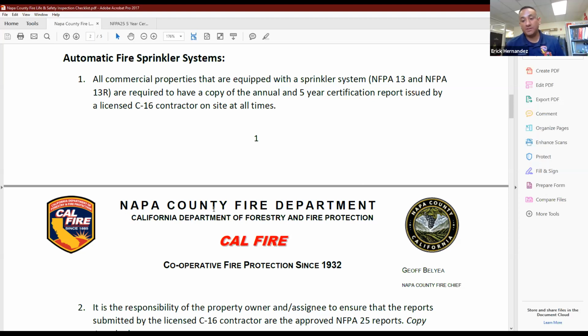So with the exception of 13D, all 13R and 13 systems are required to be inspected on an annual basis by a C-16 contractor. And in addition, a 5-year inspection report shall be issued. And these records shall be kept on site and be ready in case our office is looking for those, asks for those inspection records.